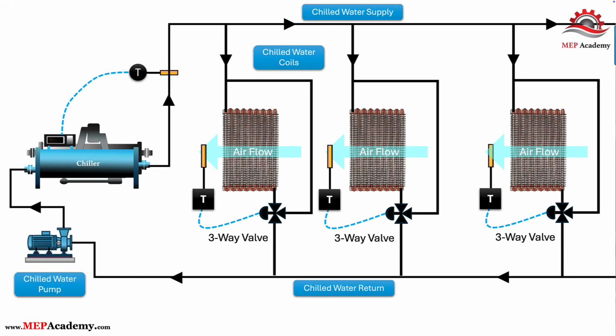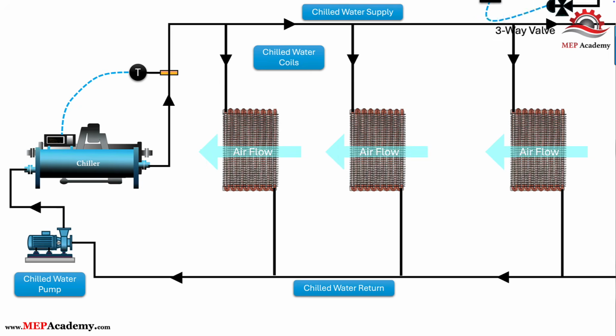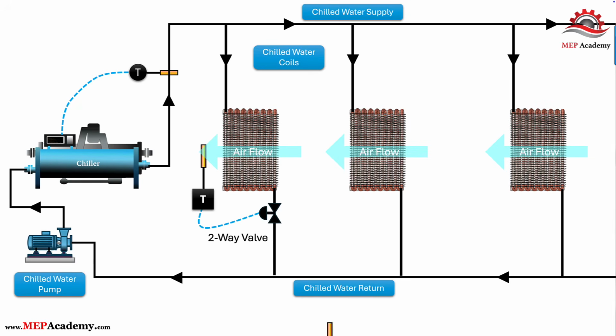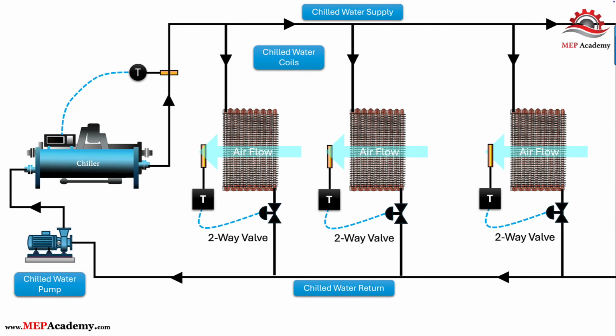The first is a chilled water pump serving a two-way valve system. Remove the existing three-way control valves and associated bypass piping and replace them with two-way modulating valves. This allows chilled water flow to vary with load instead of maintaining constant flow from the supply to the return. Install a variable frequency drive, VFD, to control the pump motor, first confirming that the motor is rated for VFD duty. If the motor is not VFD rated, it must be replaced.